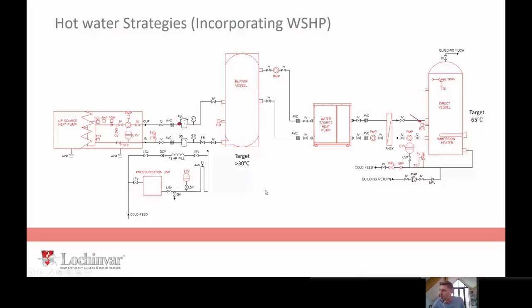Same situation, but for hot water, except if you're doing it for hot water, chances are you're designing some kind of process plant, something like that. You need really high hot water temperatures, but you need them efficiently. It might be like a bovine processing facility, so you need to spray it down with ridiculously hot sanitary hot water temperatures to make sure that you're cleaning everything down and disinfecting effectively.